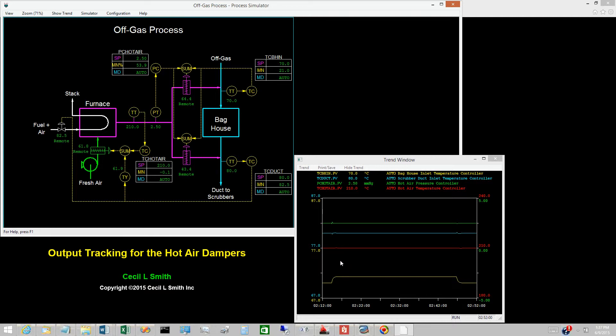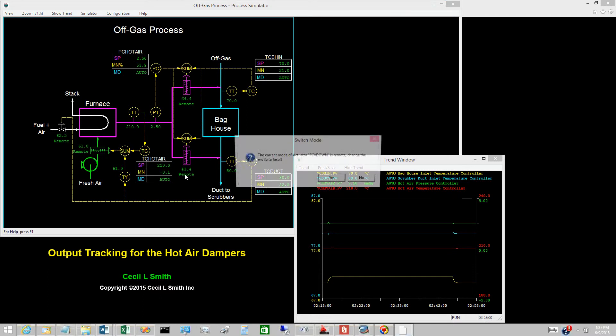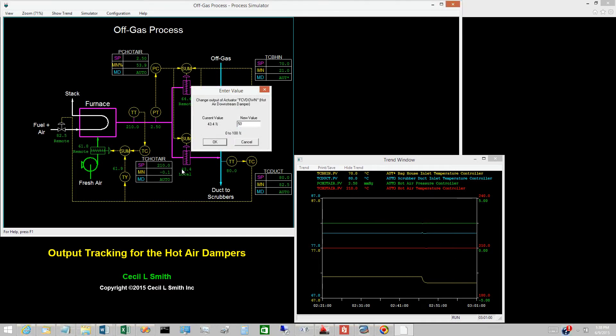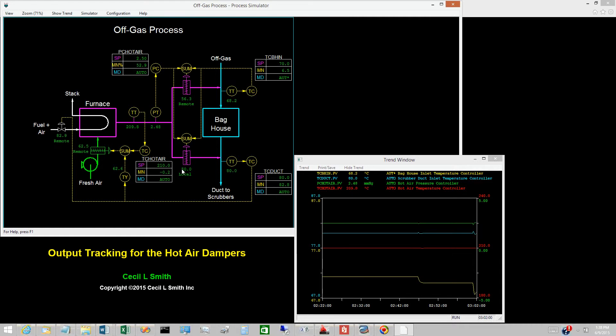Switch the hot air damper to scrubber duct inlet to local. The mode of the baghouse inlet temperature controller is indicated as AUT*, so tracking is active. The mode of the hot air pressure controller is auto, so this loop is functioning. Change the opening of the hot air damper to scrub duct inlet to 50%. The hot air pressure controller responds very rapidly and restores the hot air pressure to 2.5 millimeters of water. However, the baghouse inlet temperature is not being controlled, so it drops to 68 degrees Celsius.